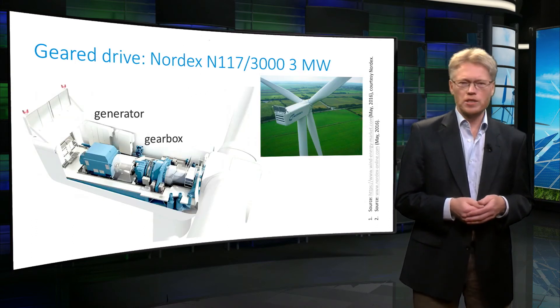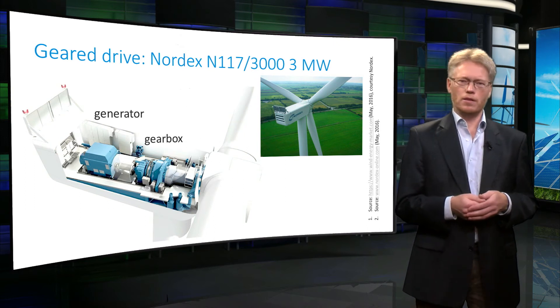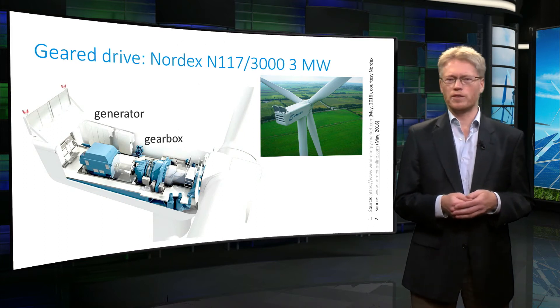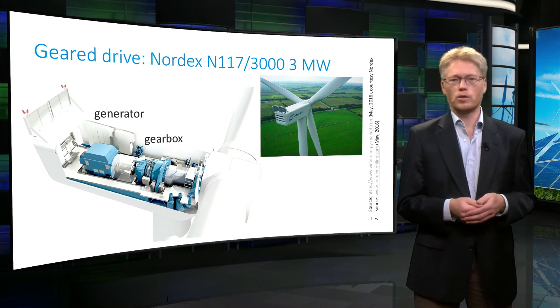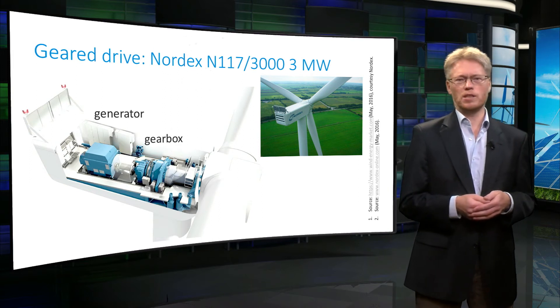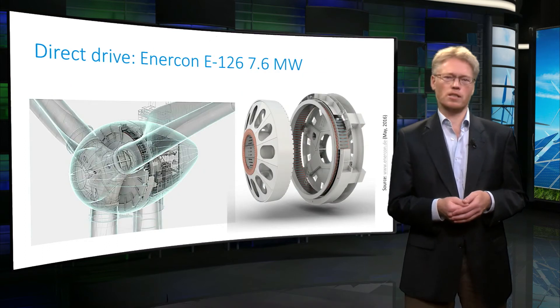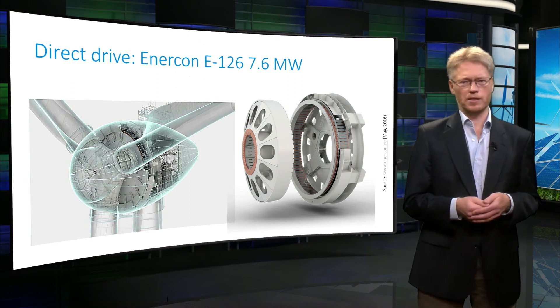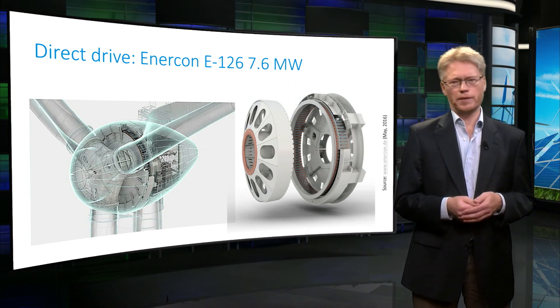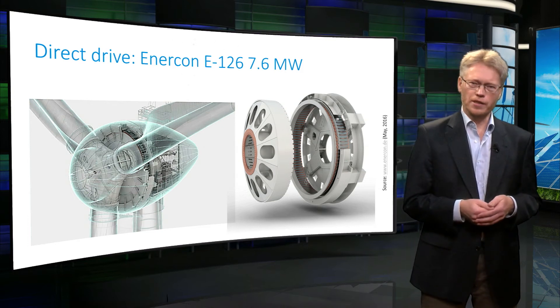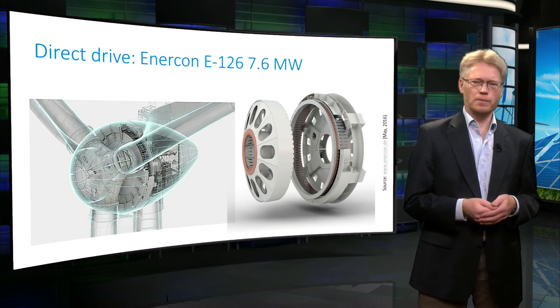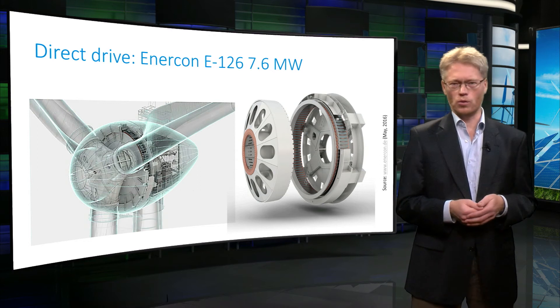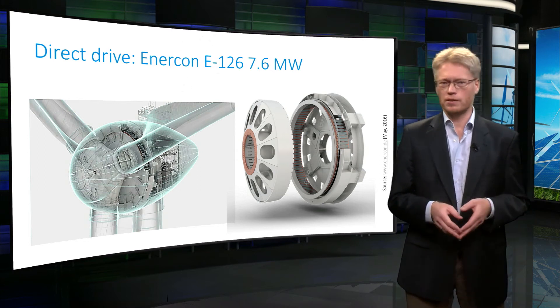As an example of a wind turbine with a geared drive, the 3 MW Nordex N117 is depicted. We see the typical form of the nacelle of such a wind turbine. We also see the gearbox and the compact high speed generator. As an example of a direct drive wind turbine, the 7.6 MW Enercon E126 is depicted, together with the generator of this turbine. As said earlier, direct drive generators are very large. In this case, the diameter of the generator is in the order of 10 meters. Because the generator is so large, the nacelle is built around this generator, giving it a different form.